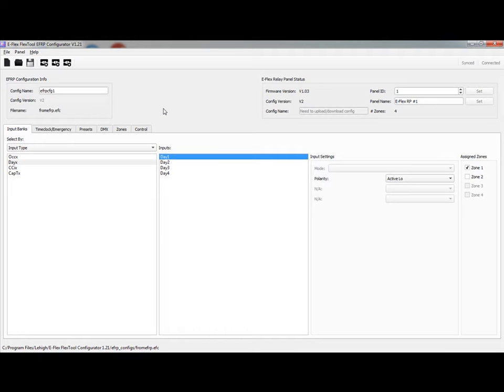In this video, we'll show you how to adjust for a secondary daylight zone. Sometimes there'll be configurations where there's a single daylight sensor, there's a primary zone that's close to a window, and then a secondary zone that's farther into a room that will still benefit from some daylight control. But we need to adjust it because we don't want to trim it too much using the same daylight sensor.